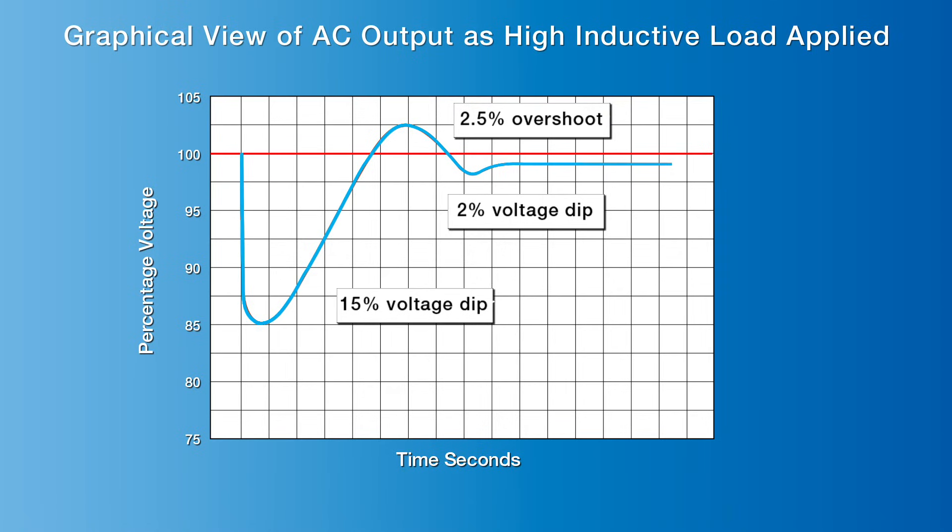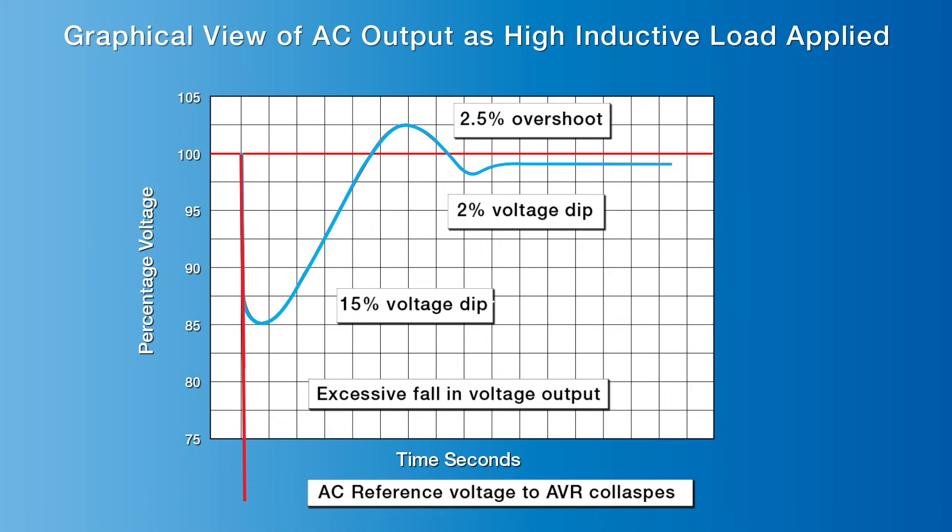However, should the inductive load on the generator be too high, such as more than 50% of generator output, the current required to start the motors will cause an excessive fall in generator voltage output and reach a point where there is insufficient reference voltage to the AVR, and hence not enough DC current to the exciter, causing the excitation to collapse, and zero voltage from the main stator.